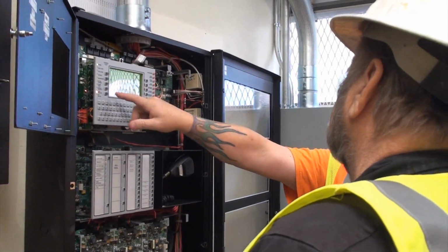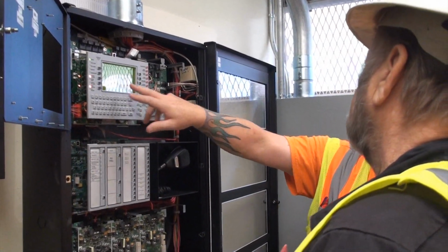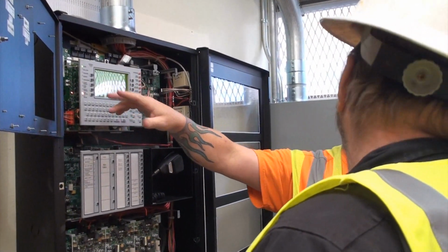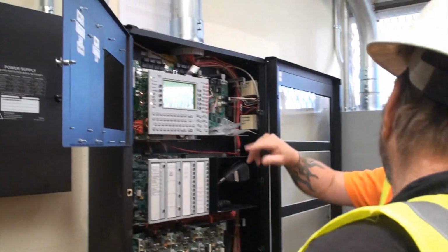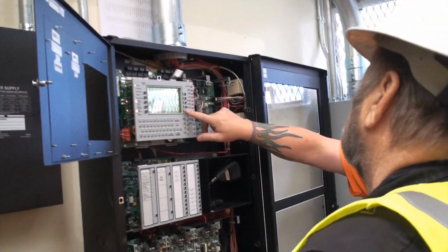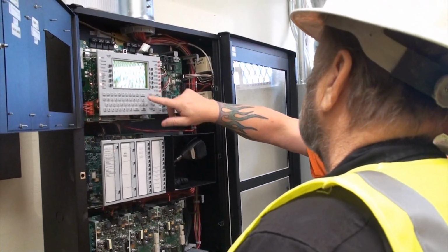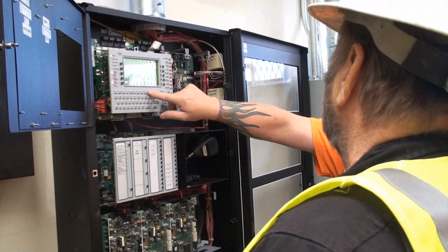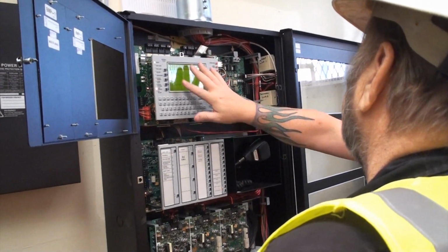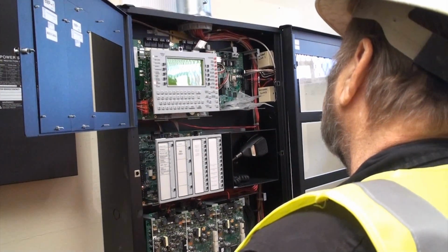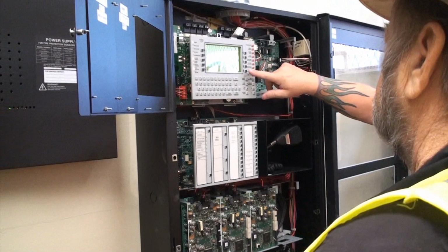You can hit that. Put that module in there, and then you'll hit accept, and then it'll say force on. You can force it on and activate it without actually sending it into alarm. And then if you want to get into the actual program part of it, it's just 8 zeros, and then you have full access. So you can put program, panel program, all that jazz.